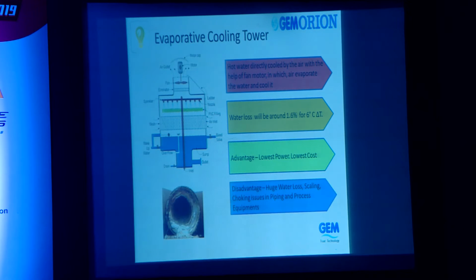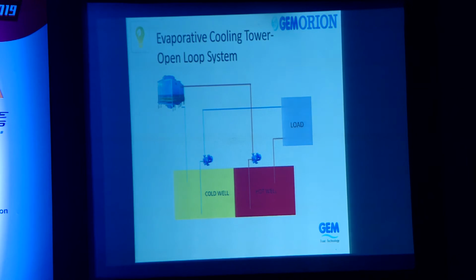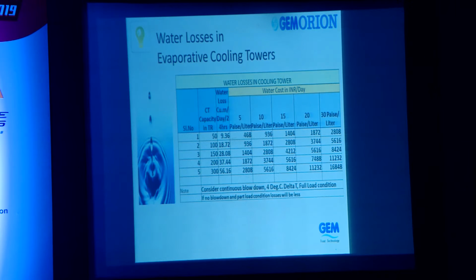So because of this, we have to select a proper system. This is a conventional evaporative system where we have the load directly cooled, with cooling tower water pumped into the process. To give you a rough indication, we have just indicated for a cooling tower of, say, about 100 TR or 150 TR, what will be the evaporation loss, and at 5 paise, 10 paise, 15 paise, 20, 30 per liter, how much is the cost?